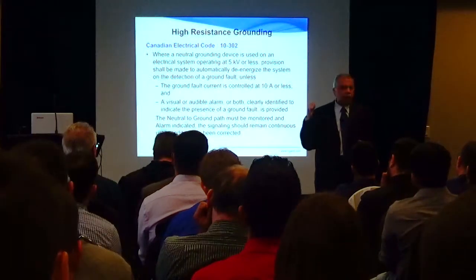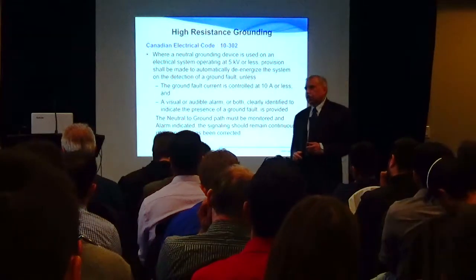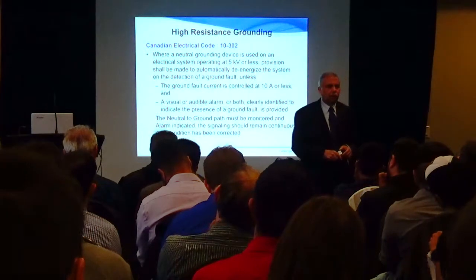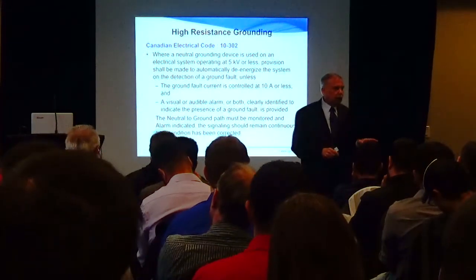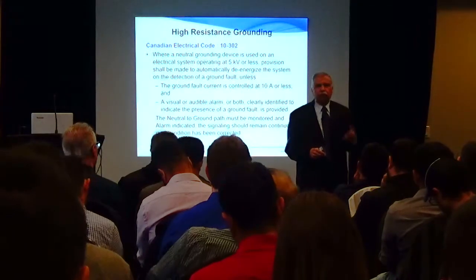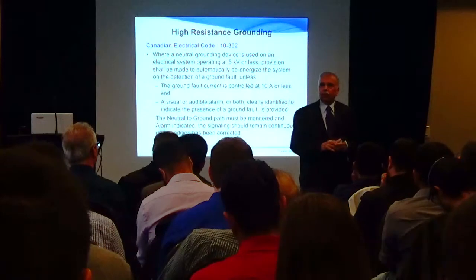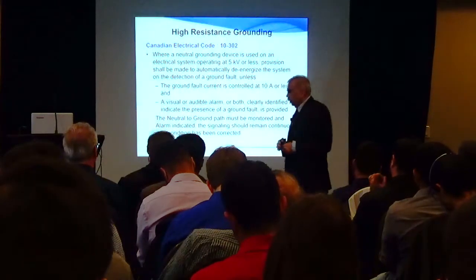So they have added a requirement for you to monitor the resistor continuously and indicate that the resistor is not in good shape. Okay? So this requirement has been added in the 2018 version of the code. So now when you use resistance grounding, you have an additional thing to do, not just the resistor, but also monitor the resistor at the same time.